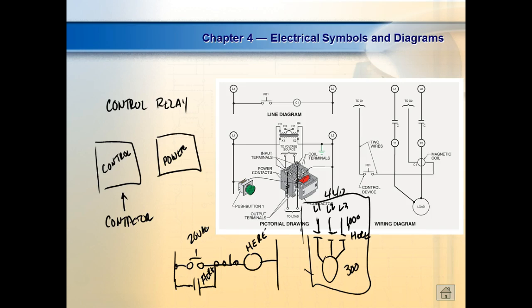You understand that? That's what's nice about the coil on the relay. What voltage you have to put across this thing to cause that relay to energize has nothing to do with what goes across the contact. So this could be DC over here, and this could be controlling what? AC over there. That's the beauty of the relay. What it controls, the power it controls, does not have to be the same power that's running the coil. So over here, this is the way your air conditioning system works. Your air conditioning system runs off 26 volts worth of power on your control circuit. And over here, your compressor and your blower motors and everything are all 240 volts. So all the motors inside a standard HVAC system are 240 volts.